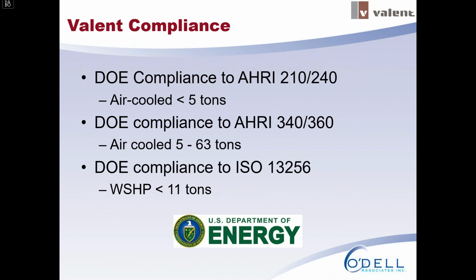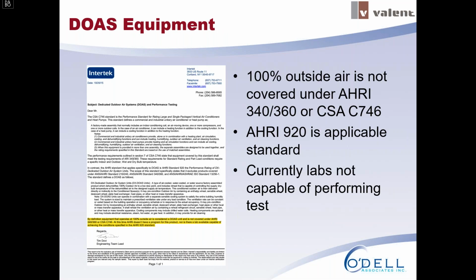What do we do with 100% outside air? I told you they adopt AHRI standard 210/240, and I also wanted to show you that a number of years ago, we went as far as going to Intertek, one of the major testers of equipment, to discover how we would test a makeup air unit or DOAS unit to AHRI and to CAN/CSA C746.